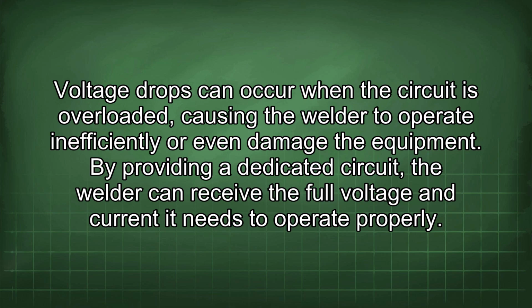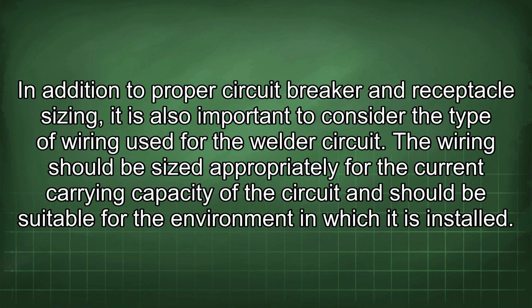Voltage drops can occur when the circuit is overloaded, causing the welder to operate inefficiently or even damage the equipment. By providing a dedicated circuit, the welder can receive the full voltage and current it needs to operate properly. In addition to proper circuit breaker and receptacle sizing, it is also important to consider the type of wiring used for the welder circuit.